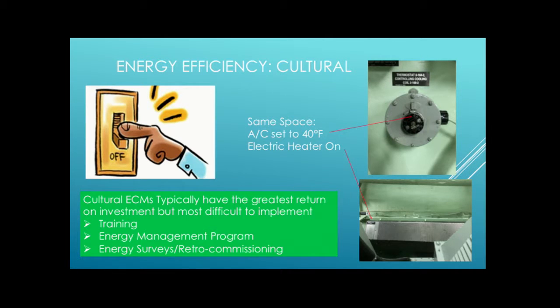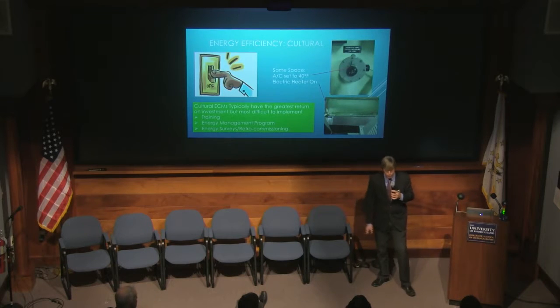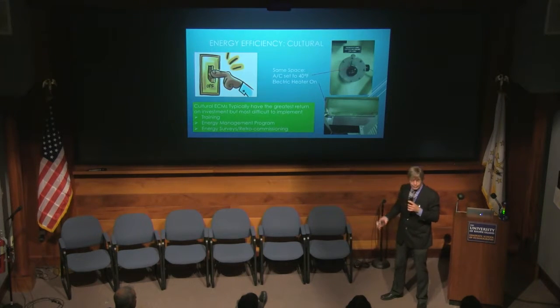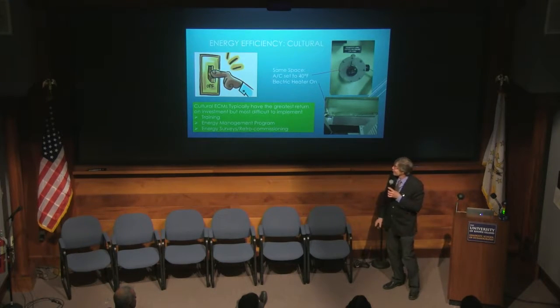I did retro-commissioning on an MSC ship, and we did some chill water reset trying to get the air conditioning turned off. By the way, it's the middle of winter. So I raised it from a 33-degree chill water temperature up to 44, and they complained that the boat was hot. I was like, well, it's 40 degrees outside, it shouldn't be hot, you're in heating mode.